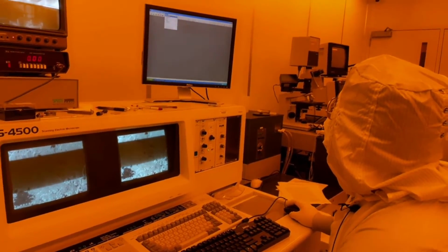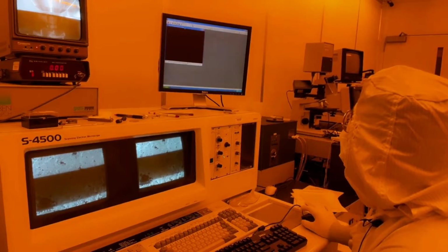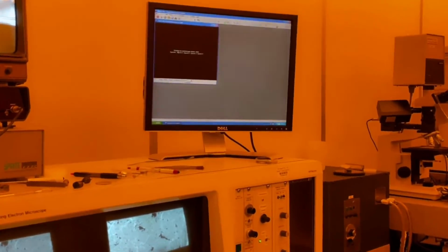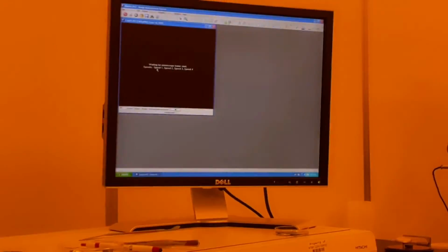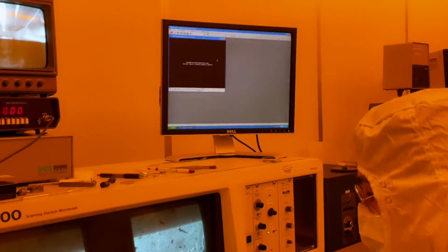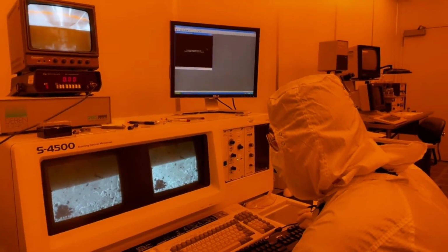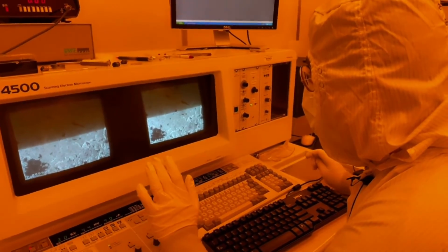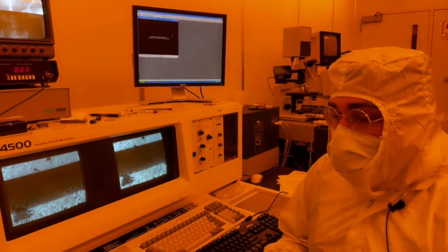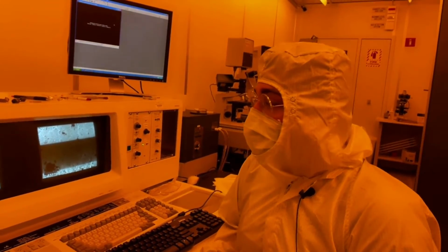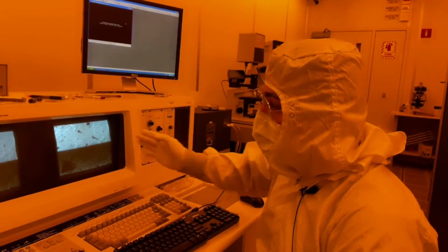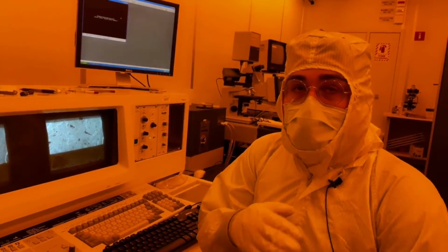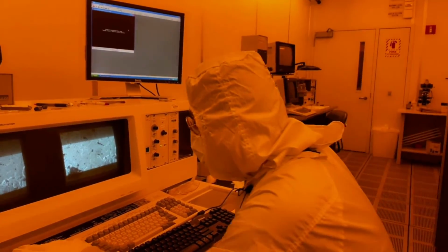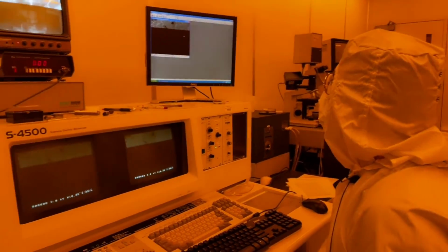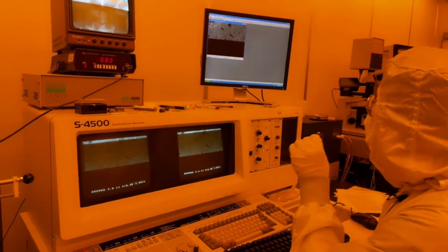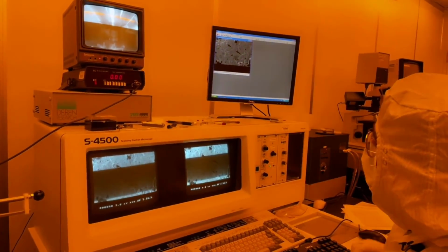To get an image, we're going to press acquire, and we're going to do a continuous scan. It says here it will only do microscope speeds of 1, 2, 3, and 4. Right now we are on a scan speed of fast TV. The slower the scan speed, the higher the resolution of our image. Essentially what's happening is the electron beam is scanning over the image more slowly so it can take in more details. So we're going to put this on 3. And as we do that, you can see we have a much higher resolution image coming out.